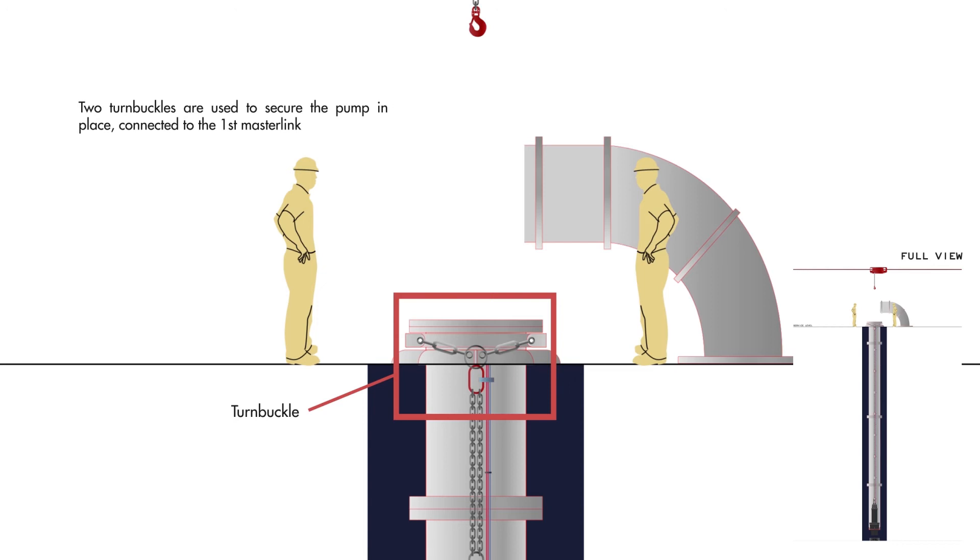Secure and tighten up the chain or wire rope in the column top with two turnbuckles in a way that prevents the chain or wire rope from moving side to side in the water flow. If the cable has been fastened to the chain or wire rope, it is important to follow the guidelines shown in the video for the cable suspension system.